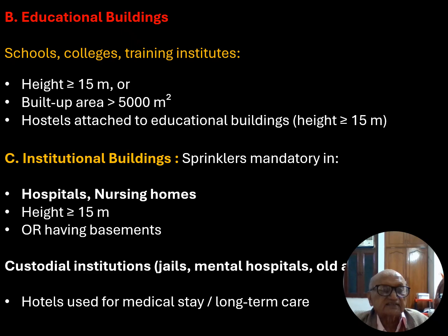Dear friends, in the case of educational buildings, that is schools, colleges and training institutes, sprinklers are required where height is more than 15 meters and the built-up area is 5,000 square meters, and for hostels attached to the educational building if their height is more than 15 meters. So these three items are compulsorily to be provided.